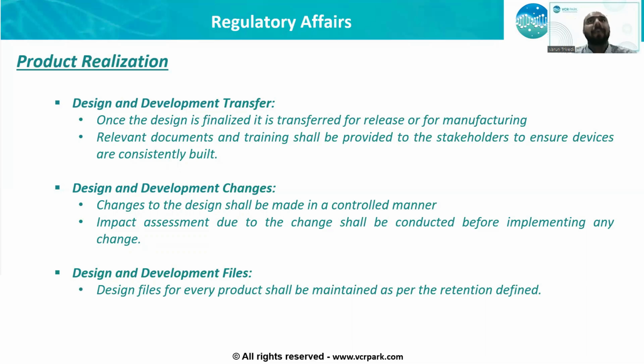Design changes. You cannot just randomly make changes to the design. As we were talking about process changes and control to the process, similarly, design changes and control to the design shall be implemented. At any point in time, if a design gets changed, relevant information needs to be appended. And most importantly, for any design change, verification shall be conducted. You may opt to not do validation if the changes are not significant in nature, but if that is the case, you need to justify the same.